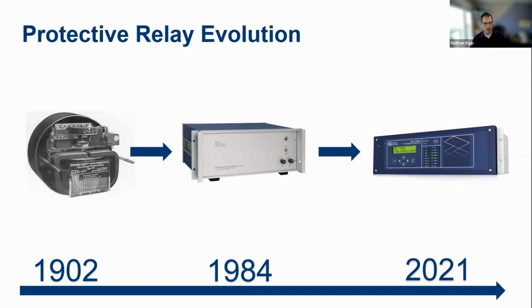In 1984, with the first microprocessor-based relay, the industry found some huge benefits, right? Prior to that, with the electromechanicals, it would know if there was a fault and it would trip if there was a fault. But if that relay is on a 100-kilometer line, someone's going to have to walk that full 100 kilometers to figure out where the fault was. And hopefully they can find signs to really easily identify where it was. In 1984, since we moved to microprocessor, we can look at the harmonics on the line, we can look at the frequencies, we can look at everything that's going on with the waves, voltages and currents, and do some fancy math to figure out that, oh, this fault on this 100-kilometer line occurred about 10% down the line, right? And so you don't have to walk the full 100 kilometers. You can look 10 kilometers down the line and say, okay, this is where the fault was, and then really narrow your search. And what this does is drastically speed up the time to clear faults and restore power for customers. So huge benefits there.